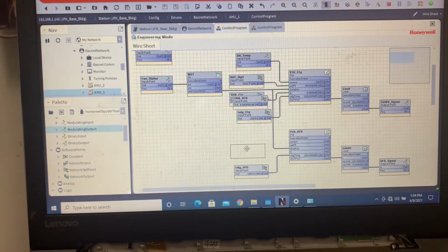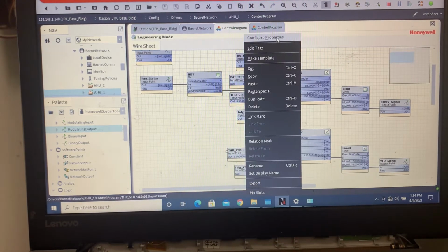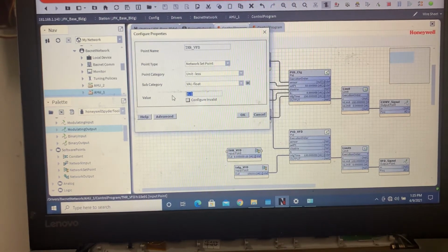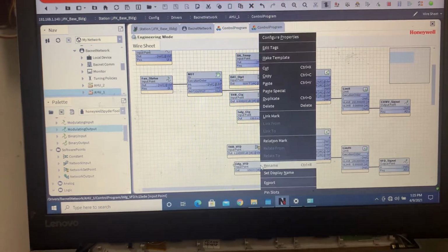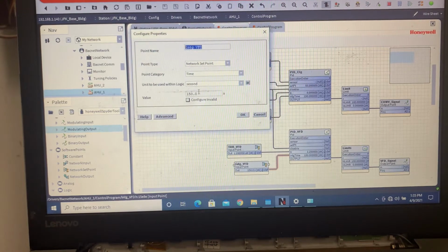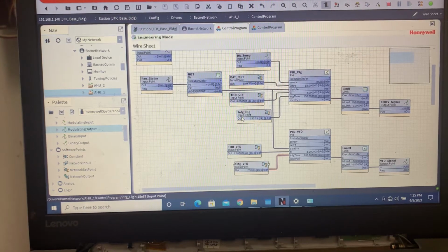Like I was saying in the earlier video, for the throttling range, we'll change that to 1.2 to start off, since with the VFD the transducer is going to be a little bit tighter on the span. And then we like to make this 200 to start off. You could do 8 to 300, it all depends on when you start commissioning, to see where everything is reading.